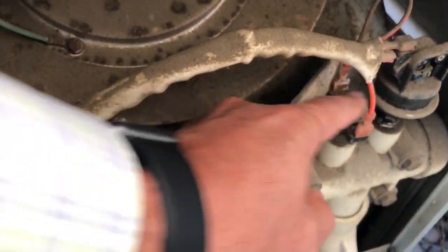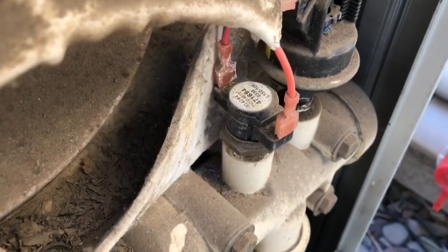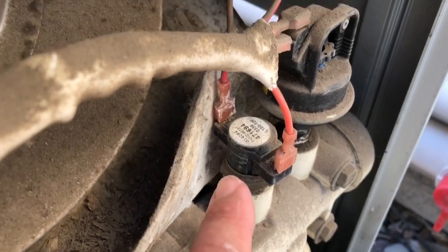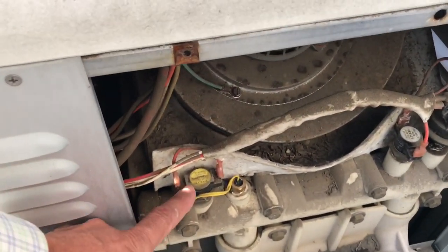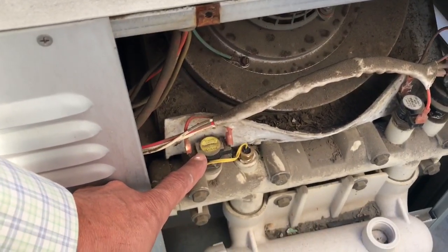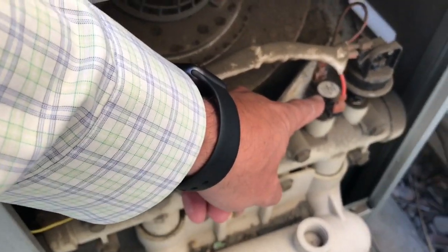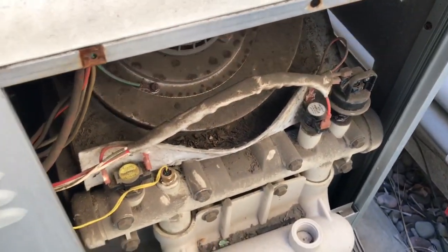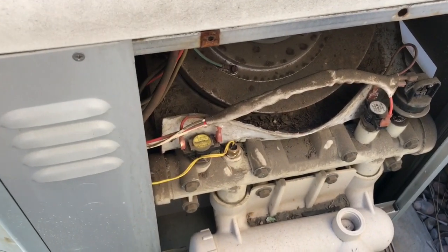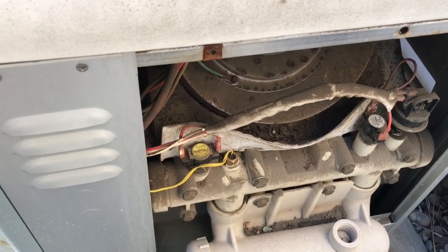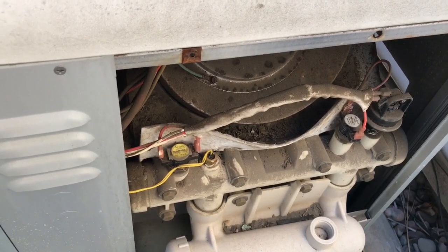This one here is the high temp switch. And again, you want to do this with the power off. There's like 24 volts going on here. If you look at that, this one is actually 150. It says L150, so it's the high temp. This one is monitoring the temperature of the water coming into the heater, and this is monitoring the temperature of the water coming out, just to make sure that the heater doesn't get too hot. So we're going to check these two switches to see if one of them is bad, and see if that resolves our E02 problem.